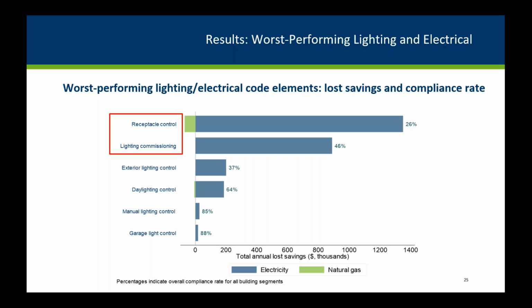However, the energy impact can be significant, as lighting is still one of the highest energy consumers in commercial buildings. Documentation of a lighting commissioning plan is lacking in many instances, which suggests that it was not planned for during design and not carried out in the field. In a few cases, lighting commissioning was included in the design specifications, but ultimately removed during construction due to building owners' concern about cost.